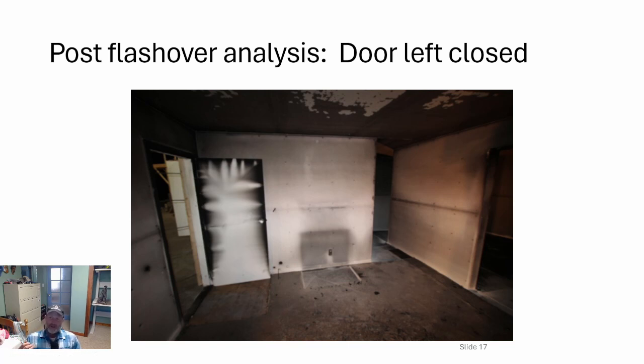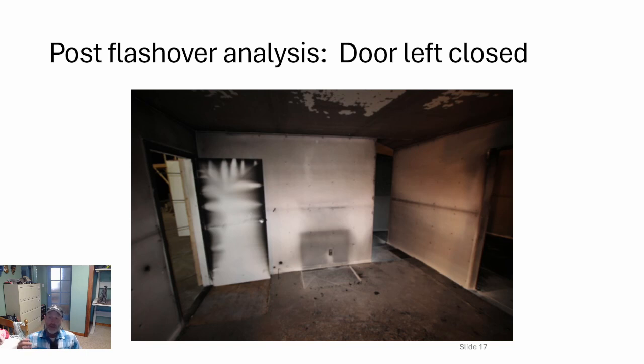Temperature and volume are directly proportional — if you double your absolute temperature, you double your volume. You can actually reach flashover in an unventilated room depending on configuration simply because of existing oxygen. There's 1.2 kilograms of air per cubic meter at ambient conditions at about 20°C. If you double the temperature of your gas, you double its volume at the same pressure, reducing density down to about 0.6 kg/m³ — so you can have complete outflow initially up to flashover.